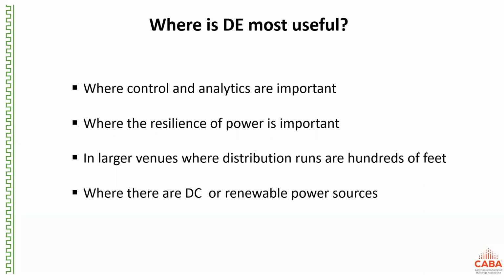For larger venues, as I explained, we have a transmitter and receiver unit. That's expensive if distances are short, but when distances get to hundreds of feet, that expense is amortized through elimination of very expensive conventional distribution systems. So the space in between becomes much less expensive to install using digital electricity.